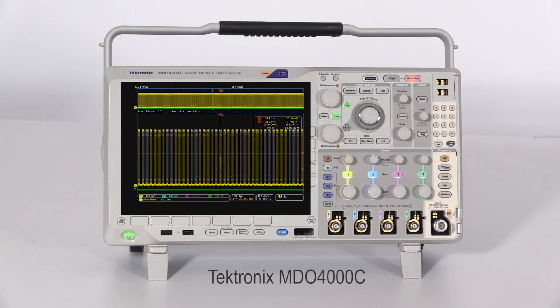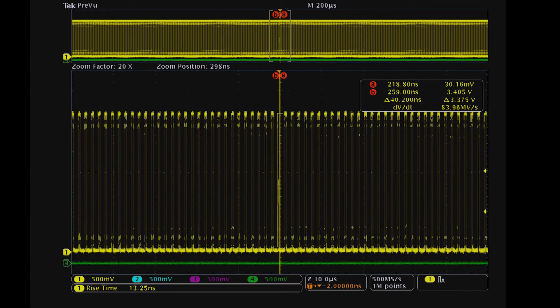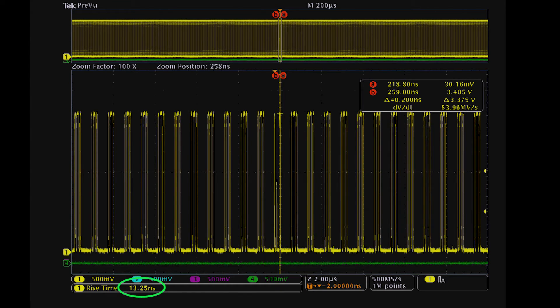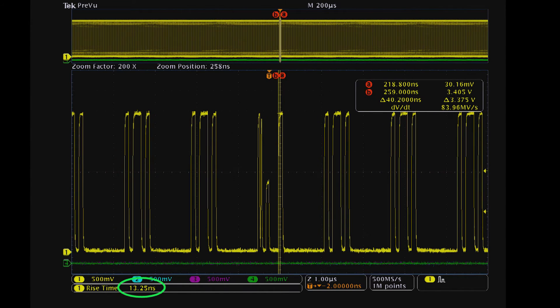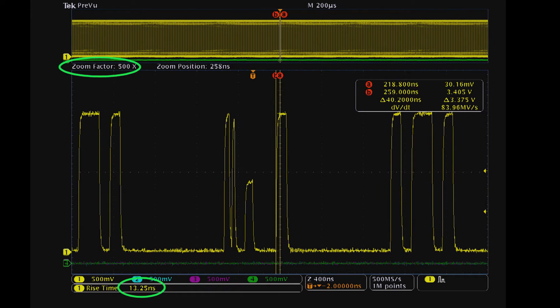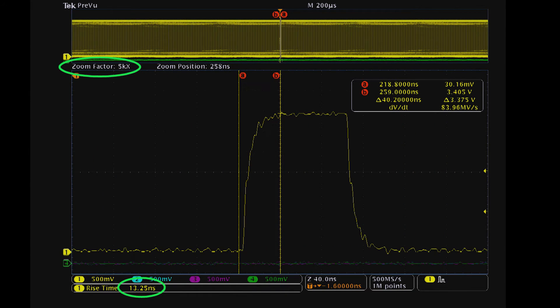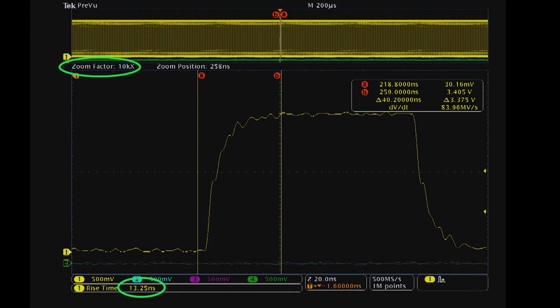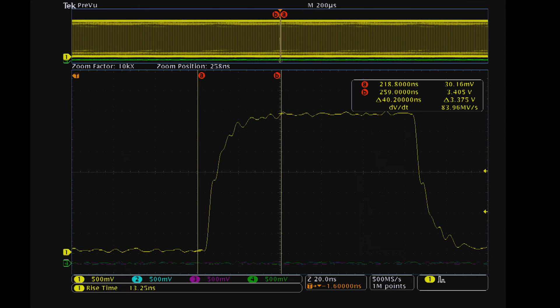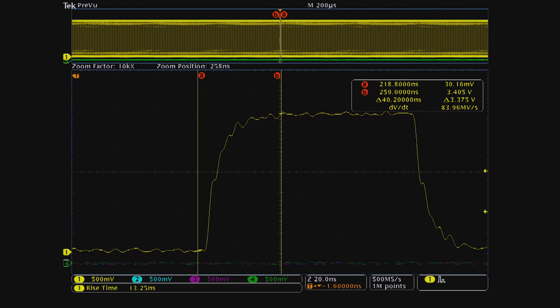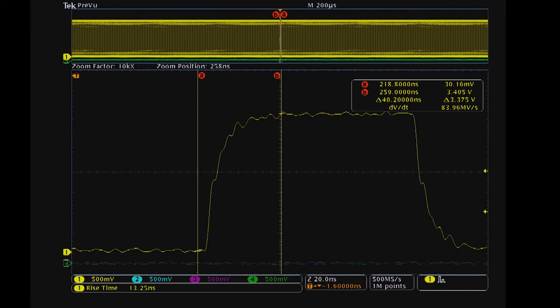As we zoom in on the waveform, the rise time measurement stays consistent at 13.25 nanoseconds. We see that the measurements of the Tektronix MDO-4000C remain the same with different zoom settings. This is because the acquisition waveform data is being used for the measurement, not the display data.